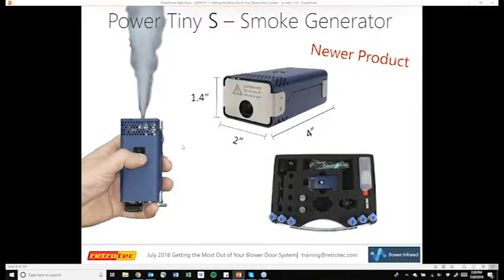It comes in this nice case, and it's basically a vaporizer. You fill these cartridges up with the fluid, and they just pop in. It comes with 2 rechargeable batteries and fits in the palm of your hand. You press the button, a big plume of vapor comes out that behaves just like smoke, and it hangs nicely in the air. So it's really good for going around and checking penetrations to see how that air is behaving with the blower door running or with a duct tester running.